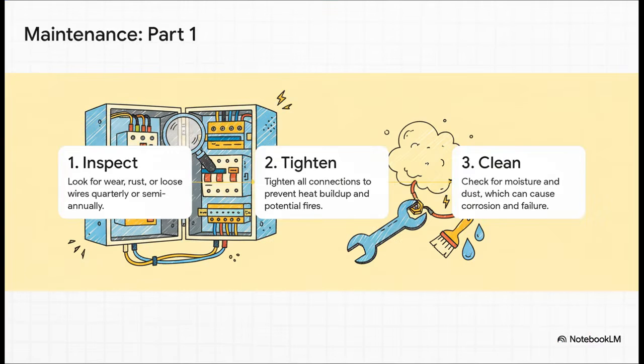Number one, just look at it. A regular inspection every few months for stuff like rust, weird discoloration, or loose wires can save you so much trouble. Number two, tighten any loose connections. This is a big one. A loose connection creates heat, and that buildup of heat is one of the top causes of electrical fires.